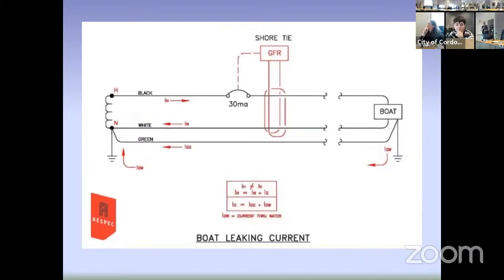Okay, this is another condition. Now all of our circuits down here in the harbor, New Harbor, will have a ground conductor. The green conductor is a ground conductor. It is not used to measure the current to the ground fault relay, but if there's a connection into the water, the current in the water will parallel the current that's in that ground conductor, and it'll still trip the circuit breaker.